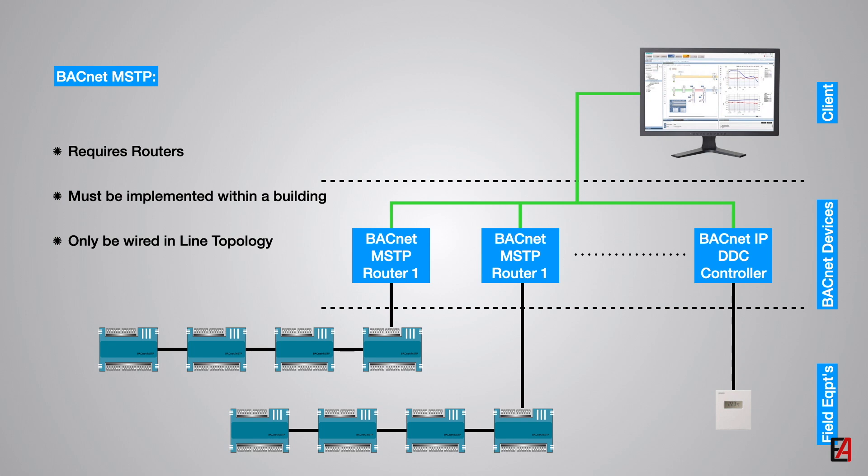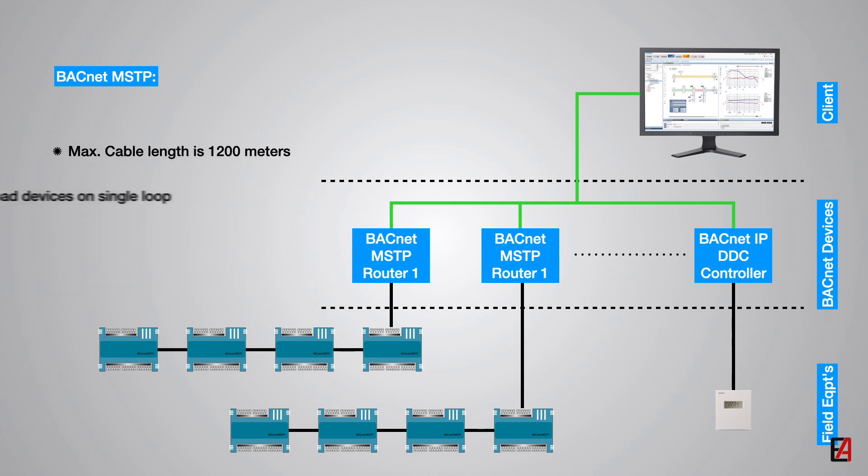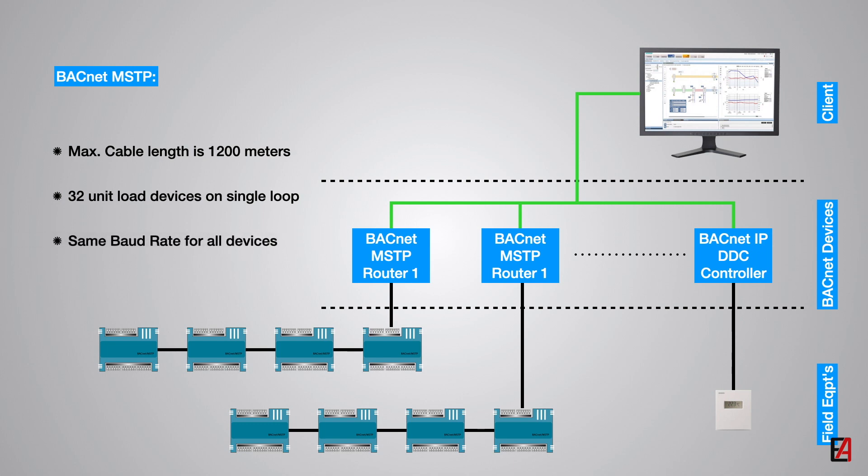T-connections, star, or tree topology wiring should not be used. Only 32 unit load devices can be connected on a single network. All devices must have the same baud rate, ensuring no single device on the network slows down the system.